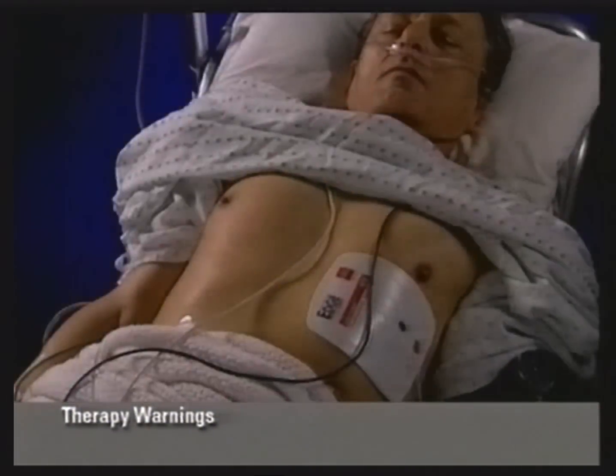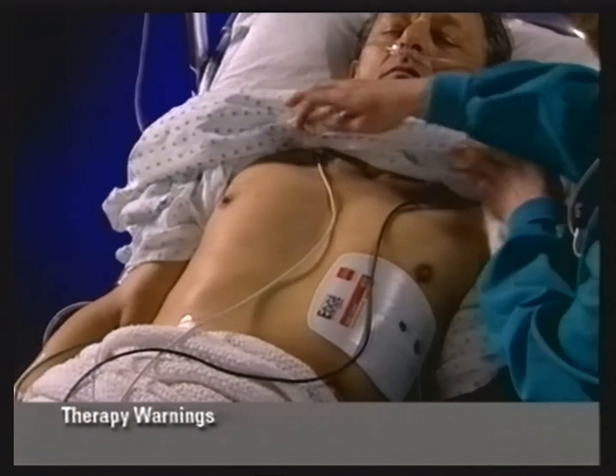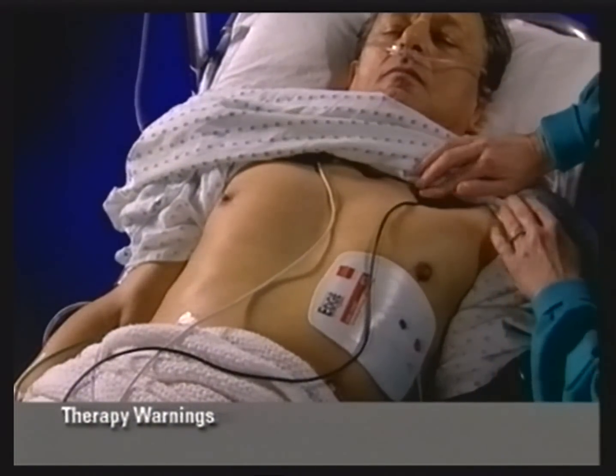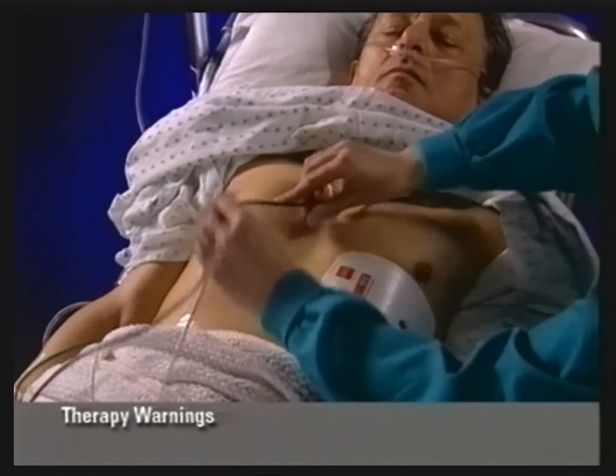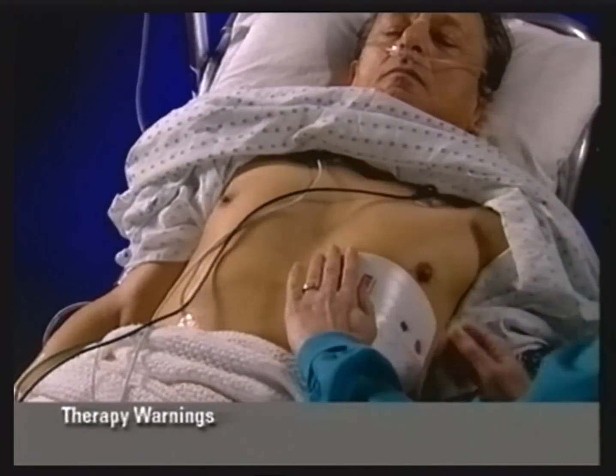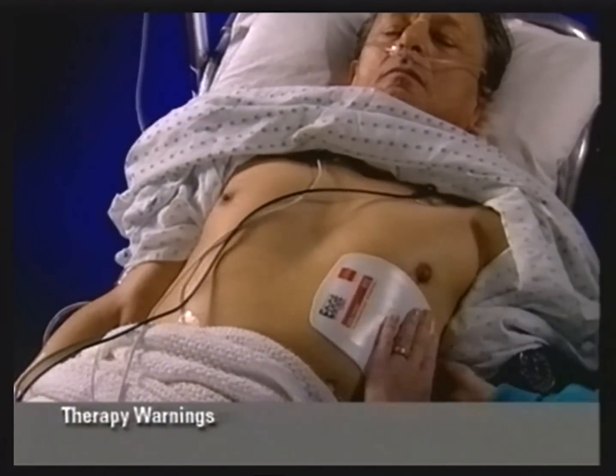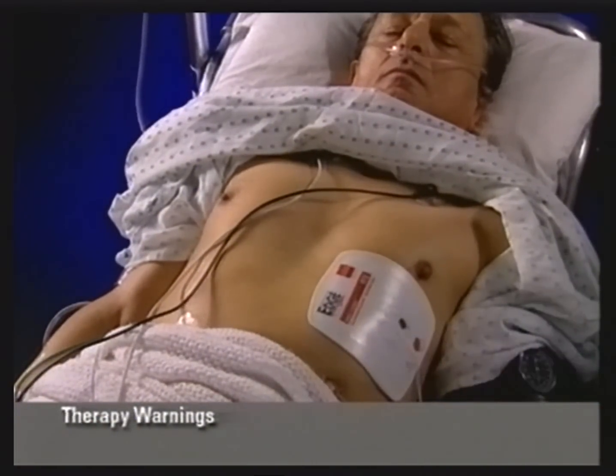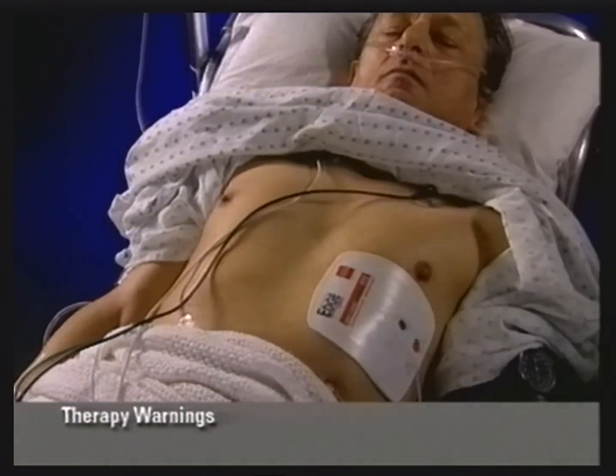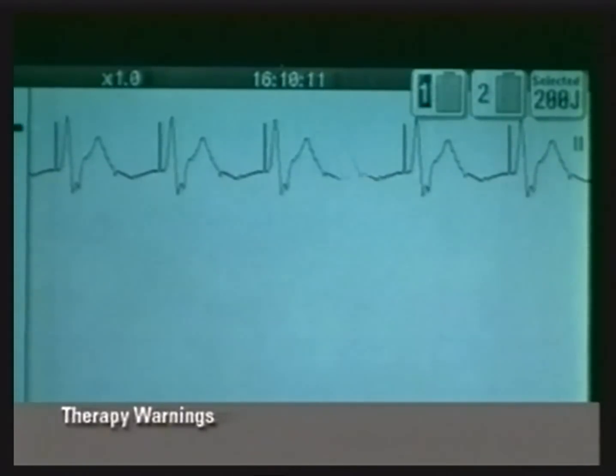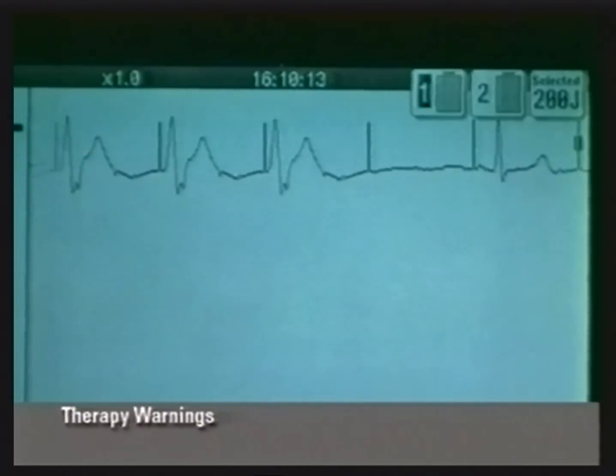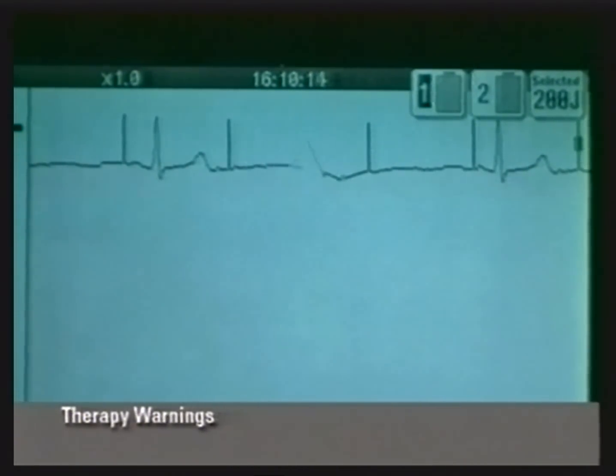Do not allow standard paddles or therapy electrodes to touch each other, ECG electrodes, lead wires, dressings, or medication patches. Contact can cause arcing and patient skin burns during defibrillation and may divert energy away from the heart. Observe the patient continuously while the pacemaker is in use. Ventricular capture threshold may change over time, resulting in loss of capture.